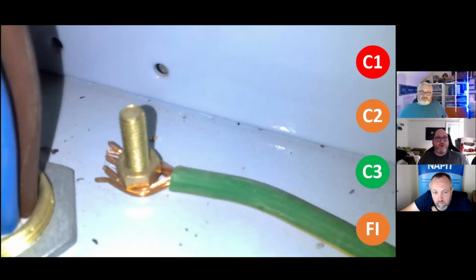So what would we do there? Would we just leave it? No, for me, that's just put a crimp lug on it or change it. Minimum would be a C3, put a copper lug on it and make that off properly. Yeah, that copper's being pulled down onto paint, so you only get about half of its surface area in contact. And if you look at the conductors on the outside, it's not going to take a lot for them to pop out of there, they're only held on by the corners. It's obviously, that's a little wiggle and that's going to let go of that, and then all of a sudden you're into reduced cross-sectional area of current carrying capacity in the event.